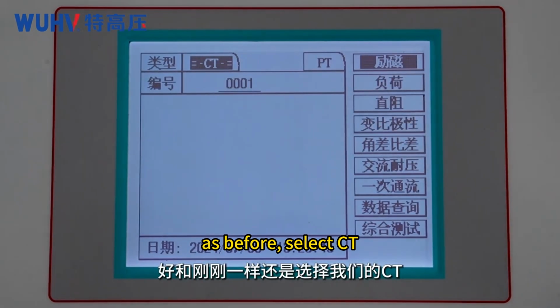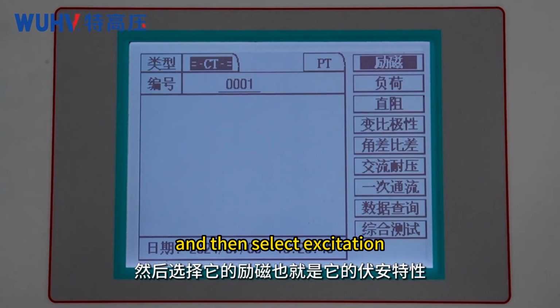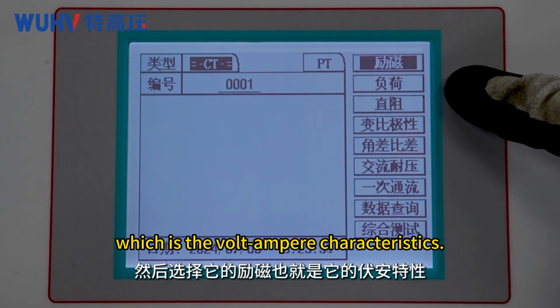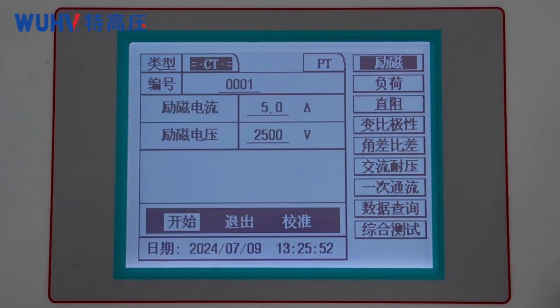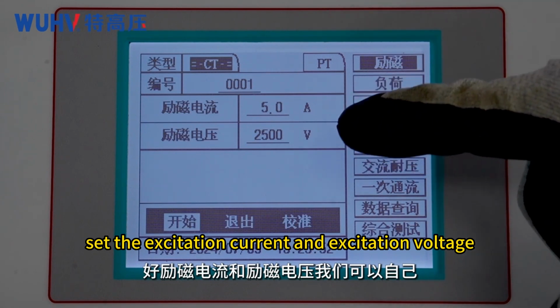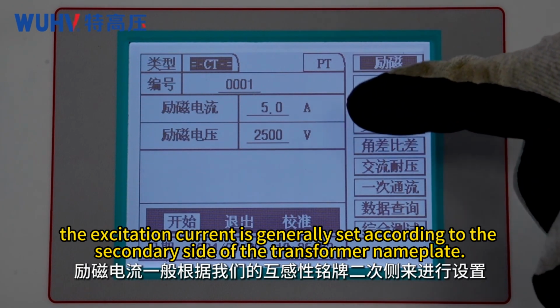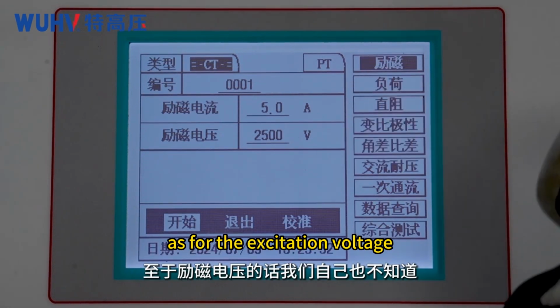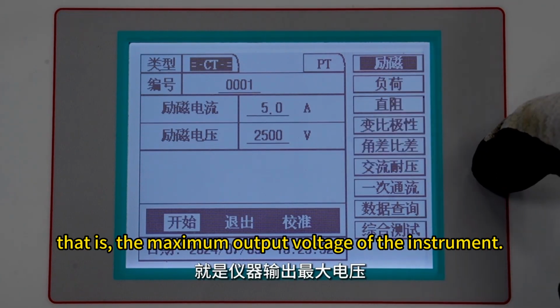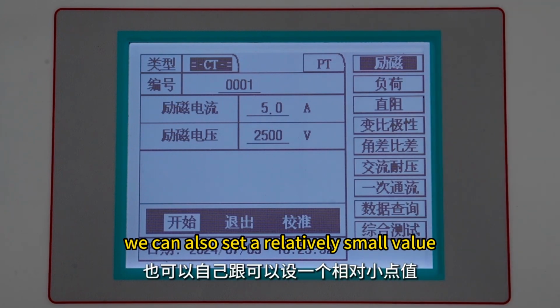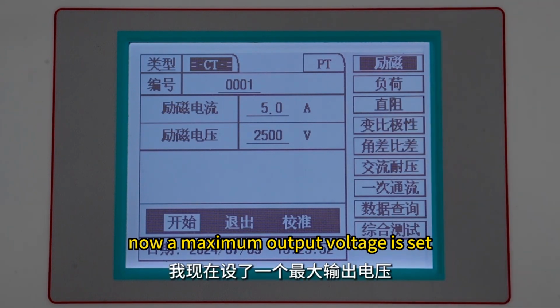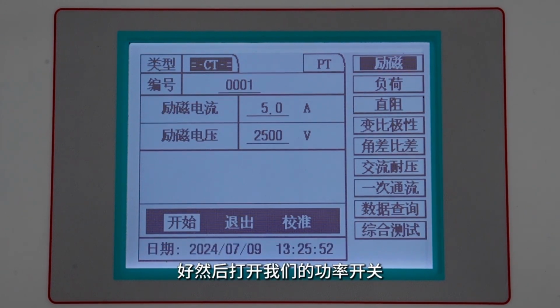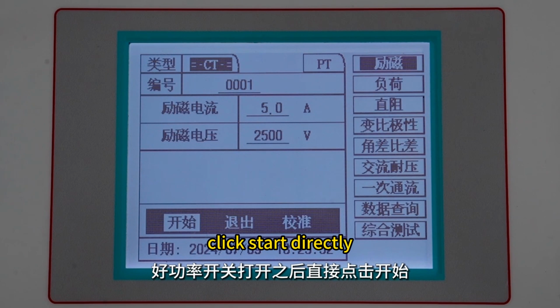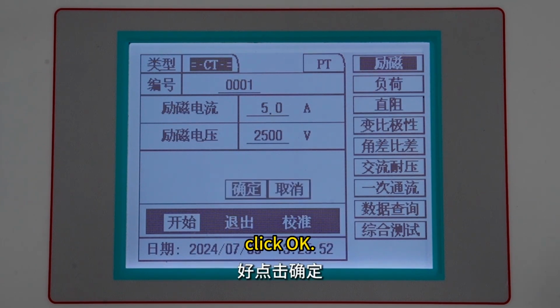As before, select CT. And then select excitation, which is the volt-ampere characteristics. Click to enter. Set the excitation current and excitation voltage. The excitation current is generally set according to the secondary side of the transformer nameplate. As for the excitation voltage, its maximum current and voltage can be set. That is, the maximum output voltage of the instrument. We can also set a relatively small value. Now a maximum output voltage is set. Turn on the power switch. Click Start directly. Click OK.